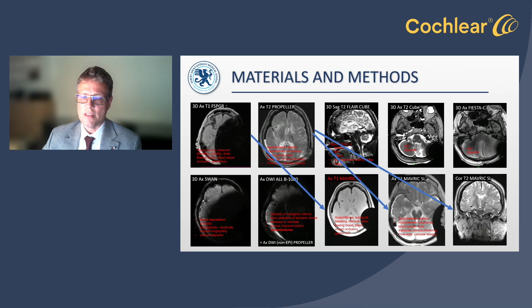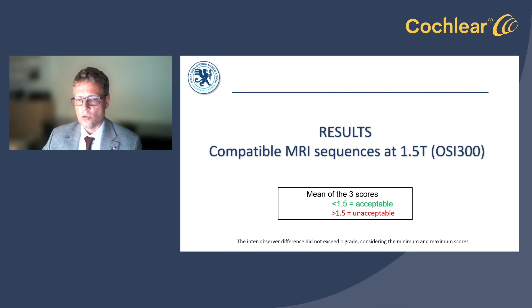Let's go to our results. For 1.5 Tesla, we took the mean of the three scores coming from the three observers. A score under 1.5 was acceptable, and over 1.5 was unacceptable. And from these results, we created a chart which looks nicely detailed. But if you take, for example, the internal auditory canal that you'd like to visualize, if you suspect the patient has an acoustic neuroma, you have a selection of sequences that you can choose from. Here you see the sequences listed, and here you see the result if the magnet is in, or if you remove the magnet and you put a spacer, or you remove the magnet and you don't put a spacer instead of the magnet.